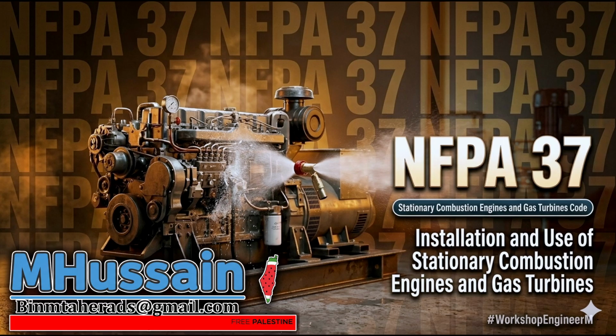Let's talk about storing all this fuel, specifically diesel day tanks. Ah, the day tank limits. This is where it gets legally interesting. So a day tank inside a shared building space is capped at 660 gallons. In a dedicated fire-rated room, it's 4,320 gallons. That's the baseline rule. But Chapter 6 contains a massive loophole. The subjective exception, as the consulting specifying engineer article called it? Yes, the code states that tanks of absolutely any size are allowed indoors if the room has, quote, suitable fire detection, fire suppression, and containment.